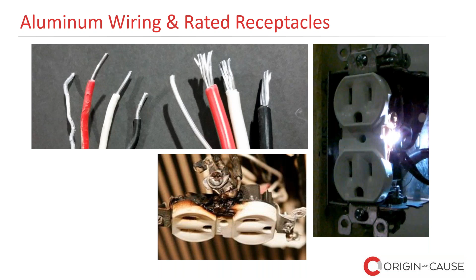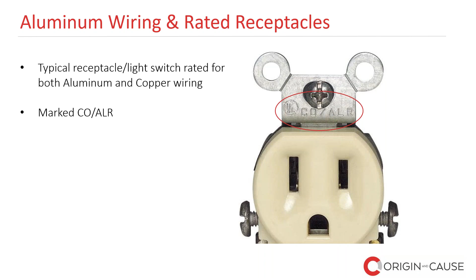Also, a very important factor is to ensure that receptacles and other devices are rated for aluminum. In fact, you will find that in many cases, they are labeled or stamped right on the product, and it will say CO/ALR or some variation indicating that this receptacle is approved to be used with copper or aluminum wiring.